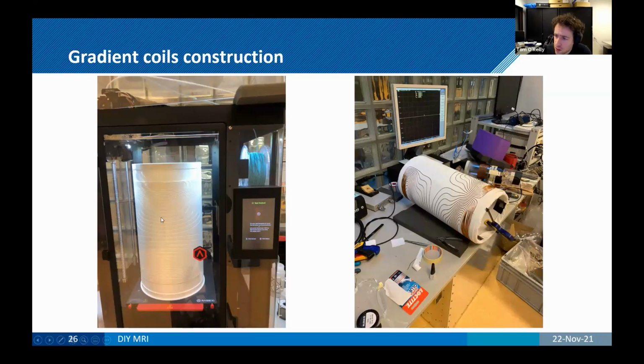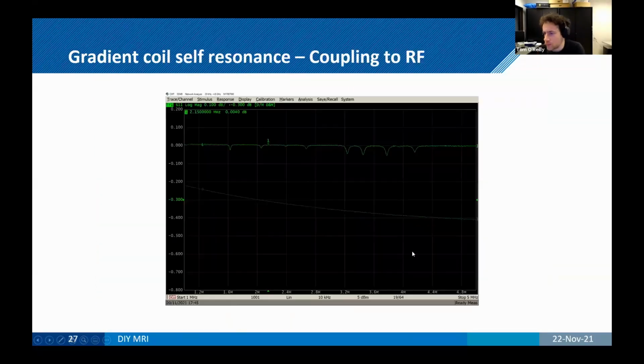We 3D print gradient formers, and then we use super glue and copper wire to basically construct the set itself. It's not that much fun to do this, but the result, it's quite easy to do. One of the things to be aware of, though, is that as with any conducting surface, your gradient will self-resonate, which means that those self-resonances will interact with your RF coils if you're not putting proper shielding in place. So make sure that you're putting a shield between your gradient coils and your RF coils, because otherwise it'll be a nightmare.